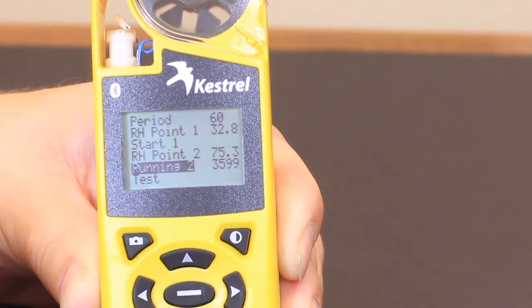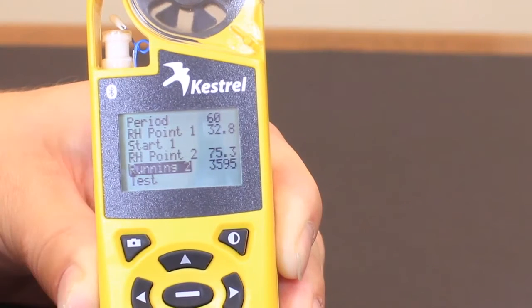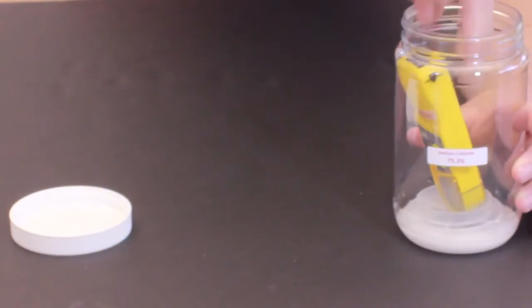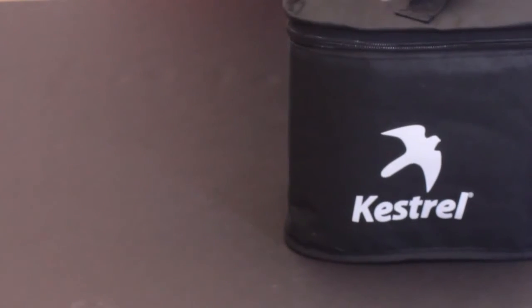Again, it'll start counting down from 3600 seconds. We're going to take the kestrel, put it now in the second calibration chamber, and wait an hour. We're going to open this up, put it in the sodium chloride chamber, tighten this up, and put it back in to leave undisturbed for another hour.